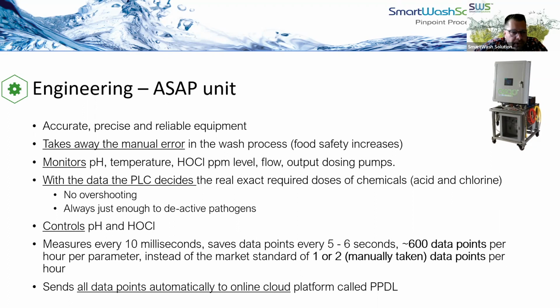That's why we are able to continuously monitor the pH, the temperature, hypochlorous acid levels, the flow, the output of the pumps, and all the data gathered by the equipment. The PLC decides the exact required doses of the chemicals at that time in the wash line, and injects that in the right spot.